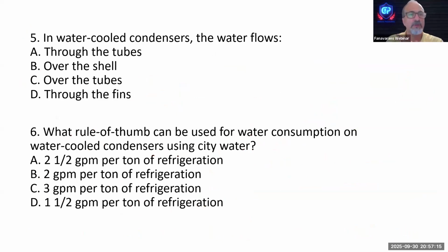So question number 5. In a water-cooled condenser, the water flows in. It's a commercial question, 313A. So when you have a chiller and the chiller has a water-cooled condenser, water flows in the shell or in the tubes? In the tubes. That's right, in the tubes. Refrigerant is in the shell, water is in the tubes. What rule of thumb can be used for water consumption of the water-cooled condenser using the city water? So we have a water-cooled condenser, and the heat rejection in the condenser is done by water, but when you use the city water, the rule of thumb is 1.5 GPM per ton of refrigeration.